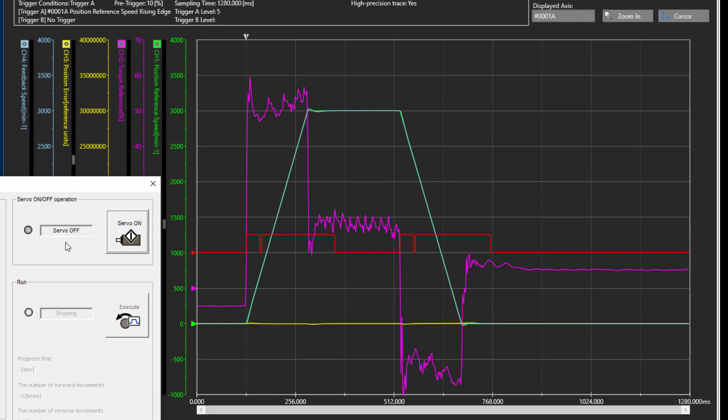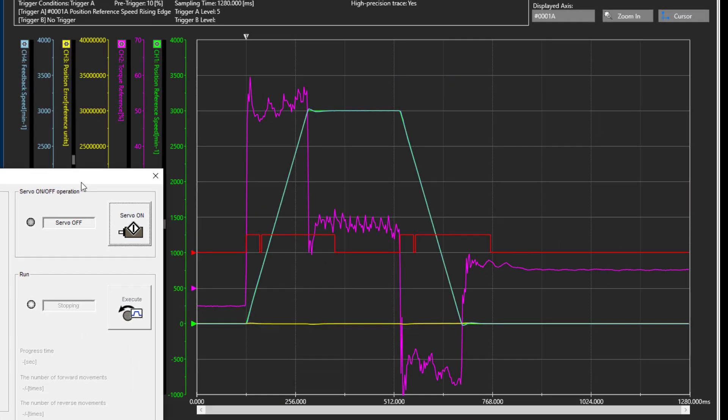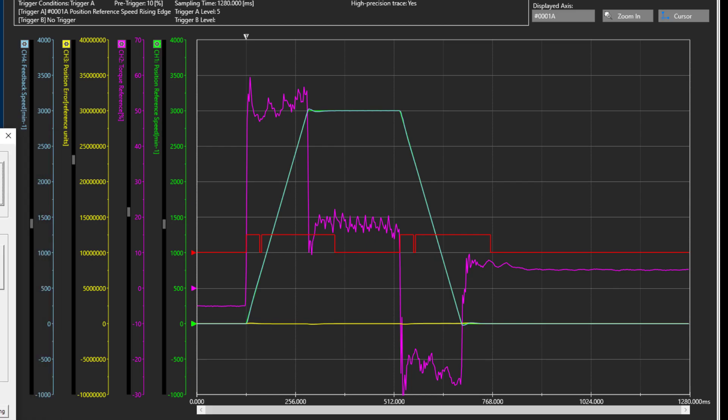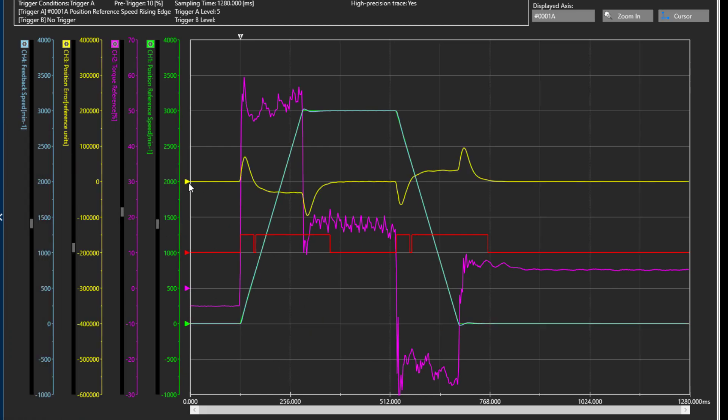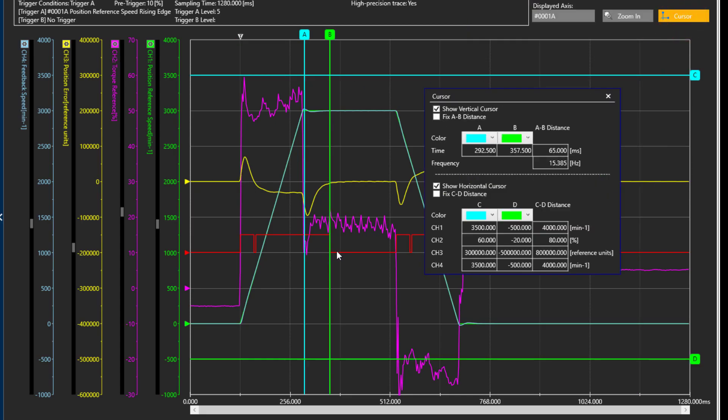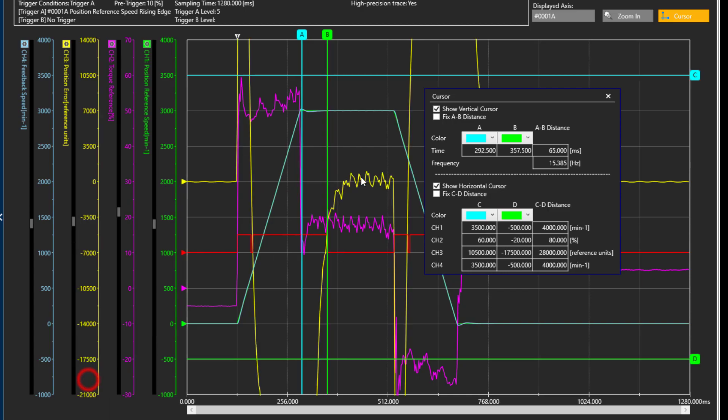The trace of this move shows the position error has been reduced quite dramatically. If you scale it, however, we'll see how much error it actually is. And with the cursors, and the coin signal here as a reference, you can see that maybe 65 milliseconds after the top speed is reached, the error is lower than that specified level. Little closer look here at the error shows that it's usually just hovering right here around zero, and not near that 4000 encoder counts. If this is acceptable for the application, then tuning is complete.